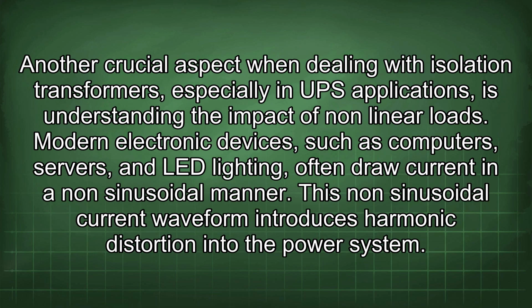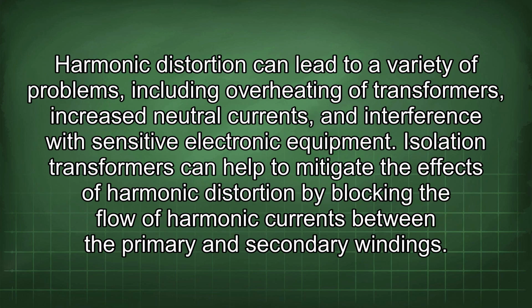Another crucial aspect when dealing with isolation transformers, especially in UPS applications, is understanding the impact of nonlinear loads. Modern electronic devices, such as computers, servers, and LED lighting, often draw current in a non-sinusoidal manner. This non-sinusoidal current waveform introduces harmonic distortion into the power system. Harmonic distortion can lead to a variety of problems, including overheating of transformers, increased neutral currents, and interference with sensitive electronic equipment. Isolation transformers can help to mitigate the effects of harmonic distortion by blocking the flow of harmonic currents between the primary and secondary windings.